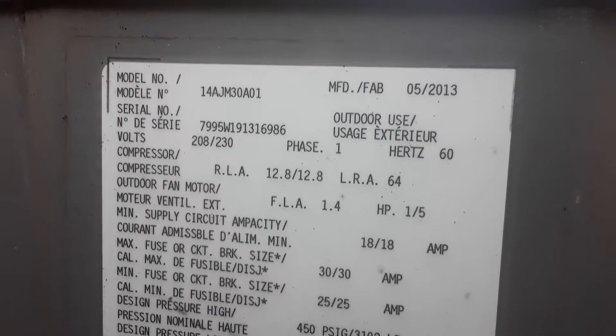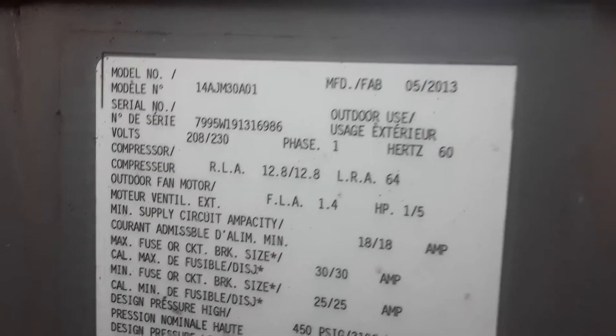Right here we have a 2013 Rheem — that's a straight cool unit. The model number is 14AJM30A01 and the serial number is 7995W191316986, so that means it's made in the 19th week of 2013.